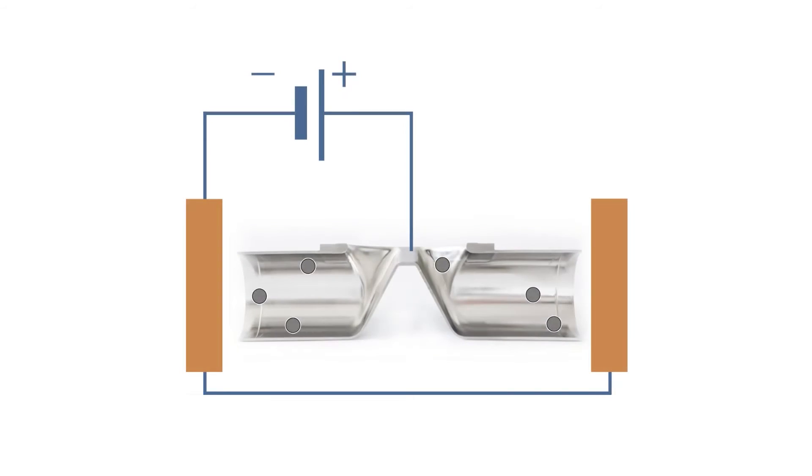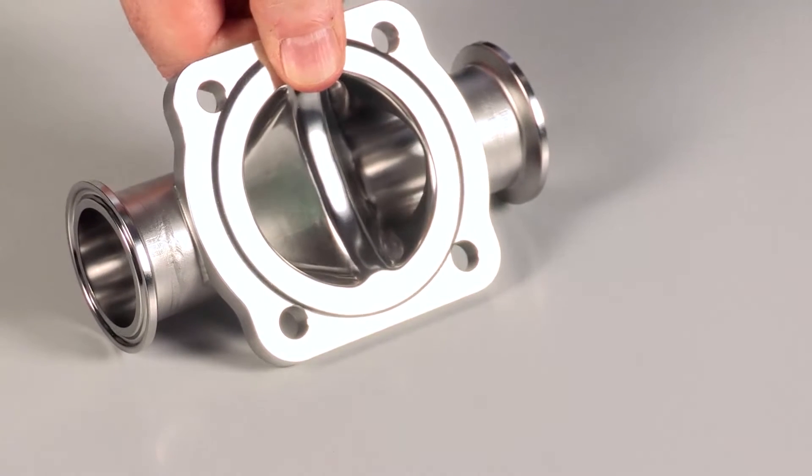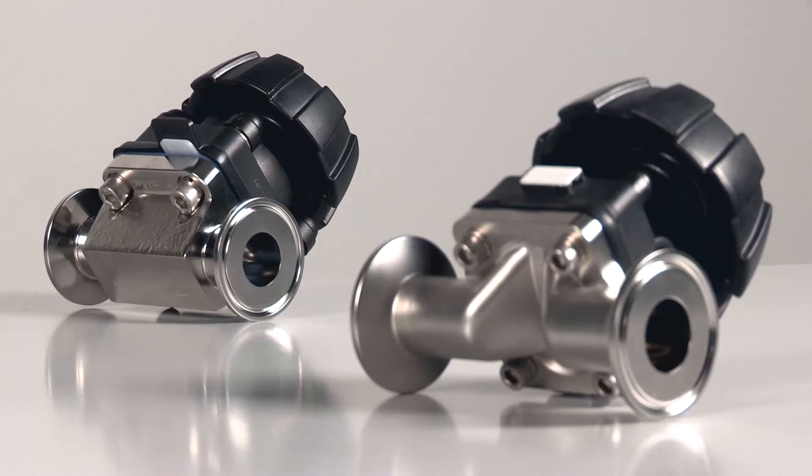This is followed by the whole valve being electropolished to give an internal finish of 0.38 microns, which also improves the chemical resistance of the tube body. Destructive pressure testing of the body results in pressures of between 90 and 250 bar — much higher than normal process pressures in the pharmaceutical industry, illustrating the mechanical strength and robustness of the body.